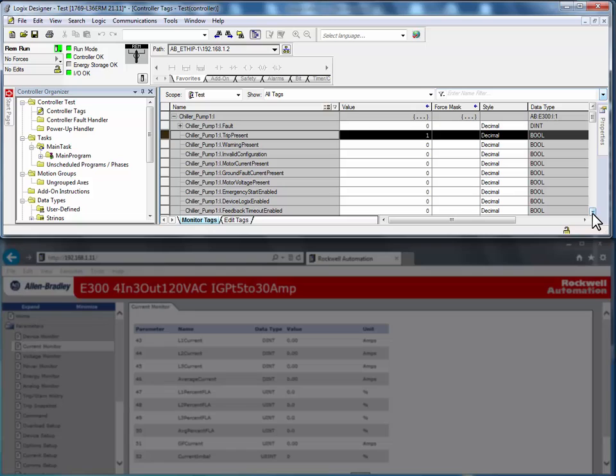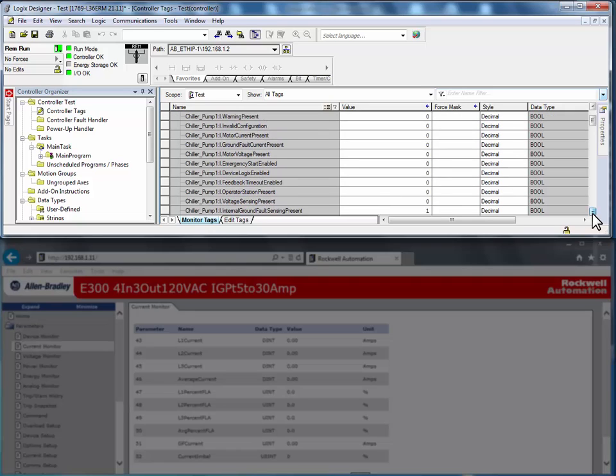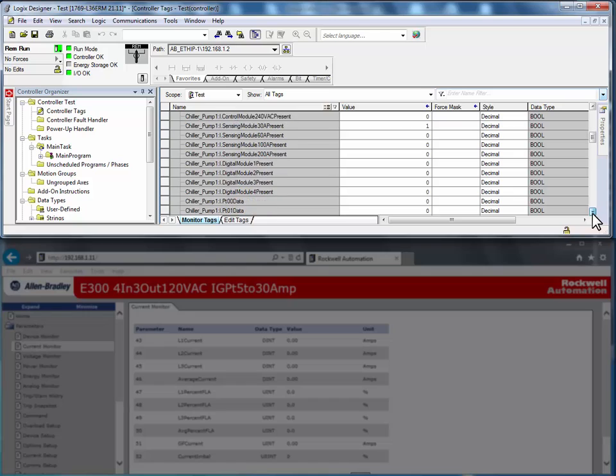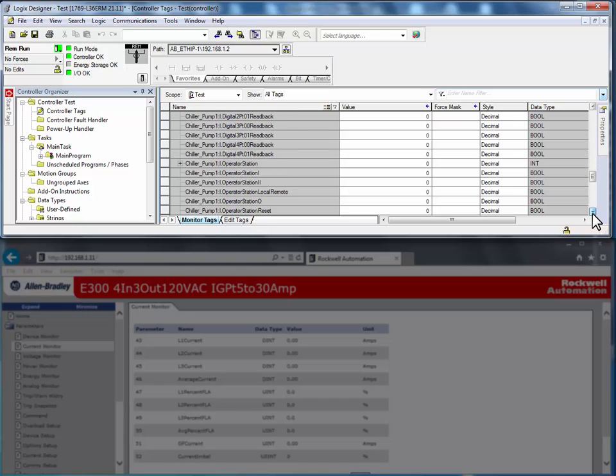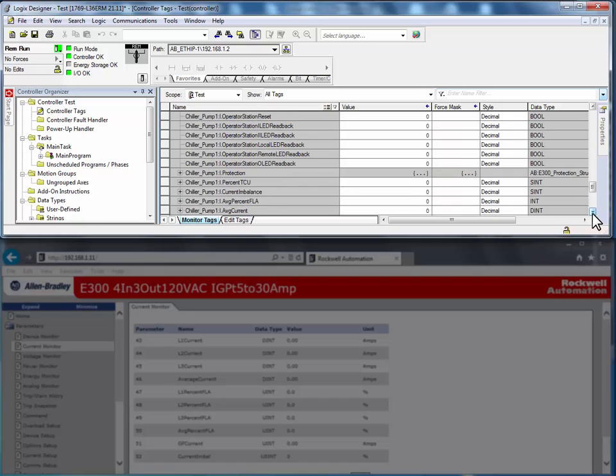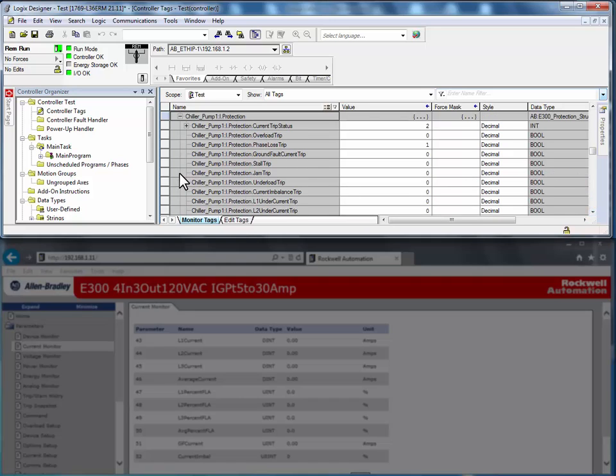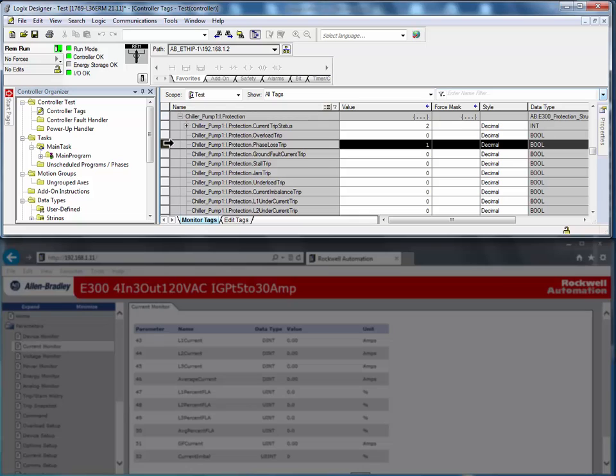We can determine the reason for the trip by monitoring the protection structure of the input assembly. The protection structure shows that the E300 had a phase loss trip.